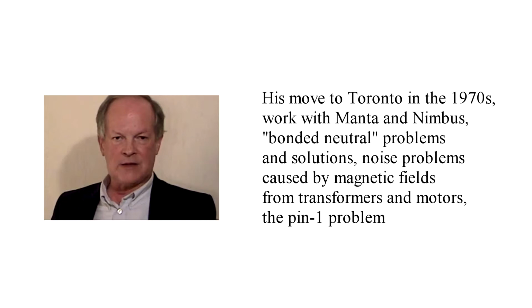And what was so stupid about this design, both of these big rooms were N1, which is the threshold of hearing. And in Philadelphia, the FOH panel was on stage right. On the back wall of the stage was the company switch for the touring sound company. They were about 50 feet apart physically. Between the front of house panel and the hydro distribution, which is on the floor below, and back around to the rear wall, there was 1,400 feet of green wire. And this is like number 4, size of your thumb. You figure out what that copper was worth. 1,400 feet. So now you take an XLR from one panel to the other, and you got hum coming out of your ears. And that was one of the problems at Philadelphia.